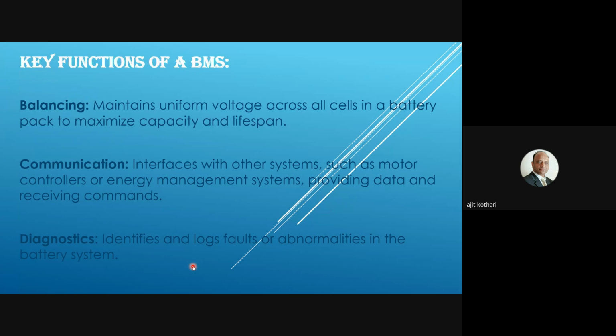Now the remaining function of BMS is balancing. As I said, balancing is a very important function in the battery bank. If all your cells are not at equal potential or equal charge, because all cells are connected in series or parallel - let's say 10 cells are connected in series, so 10 into 3.2 will give a 32-volt battery bank - if one cell is either fully charged or completely discharged, and if it is fully charged, it will not allow me to charge the remaining 9 cells, because one cell is already charged in that path, so it will not allow the charging current to flow through that path, since all cells are connected in series.